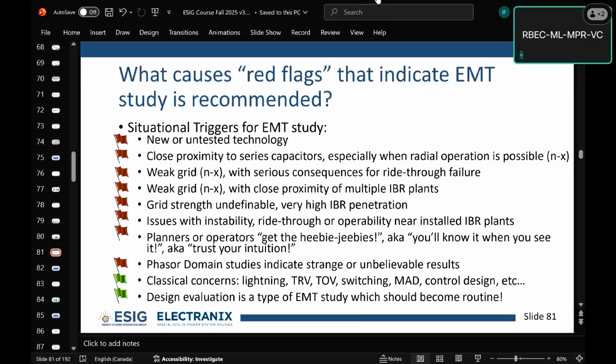One is the models that are going into the study. I can give you one example of an event where we had an event analysis. They asked us to do an event analysis, and we saw this on our DFRs and our PMUs. We say, please give us the models. They give us models. The models are perfect. As soon as we put them in our computers with an infinite bus and simulate that operating condition, we see exactly what we saw in the DFRs and in the PMUs.